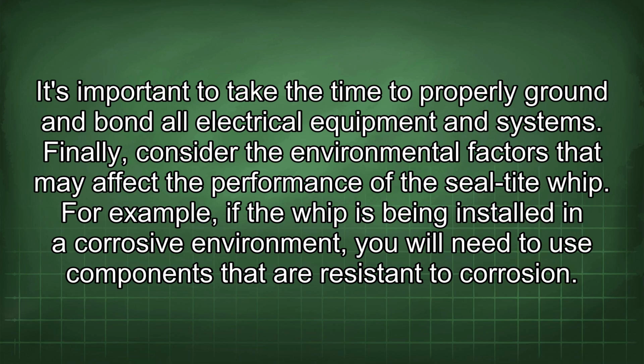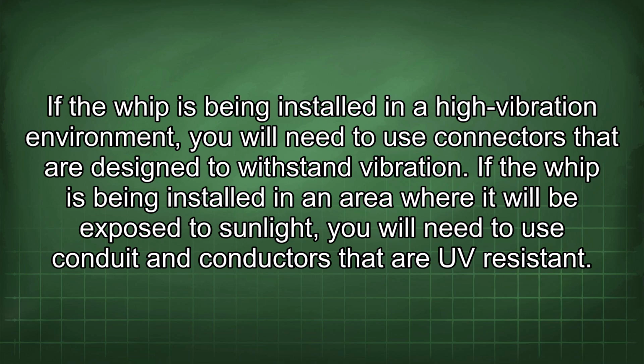Finally, consider the environmental factors that may affect the performance of the Seal-Tite whip. For example, if the whip is being installed in a corrosive environment, you will need to use components that are resistant to corrosion. If the whip is being installed in a high vibration environment, you will need to use connectors that are designed to withstand vibration. If the whip is being installed in an area where it will be exposed to sunlight, you will need to use conduit and conductors that are UV resistant.